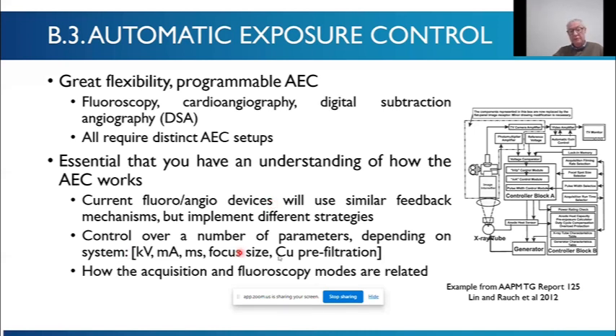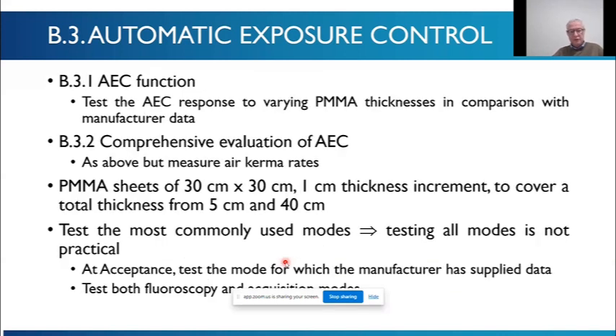The system will have control over a number of parameters, and this will depend on the imaging system. It will vary the kV, the tube current, the millisecond or the pulse length, the focus size, maybe the copper filtration as patient thickness changes. And I think you need to find out how your system is working so that you can test it properly, and also how the acquisition and the fluoroscopy modes are related. So you might select some acquisition mode, and then that will program some kind of fluoroscopy dedicated to that type of acquisition. And if you change to a different acquisition program, then the fluoroscopy mode will change. And then there'll be sub-modes within the fluoroscopy. So you could go to low, normal, or high within those modes. So yeah, understand your AEC.